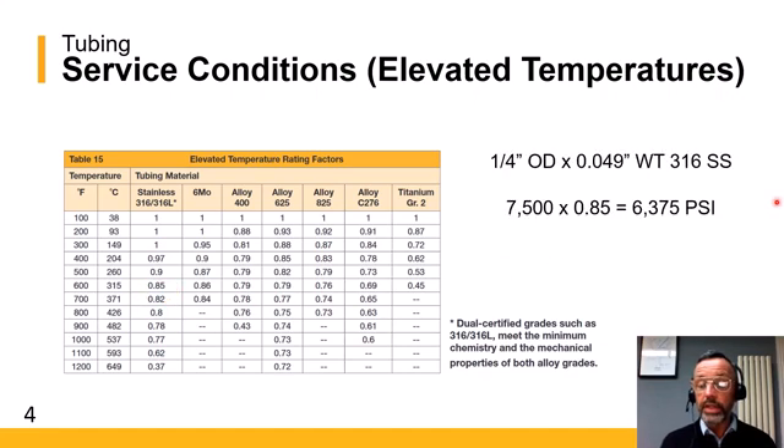Using the example we did earlier — 0.25-inch OD with a 0.049 wall thickness in 316 stainless steel — the standard tube tables gave a pressure rating of 7,500 PSI. At an elevated temperature of 600 degrees F, we apply the derating factor of 0.85, which gives us an overall working pressure of 6,375 PSI.